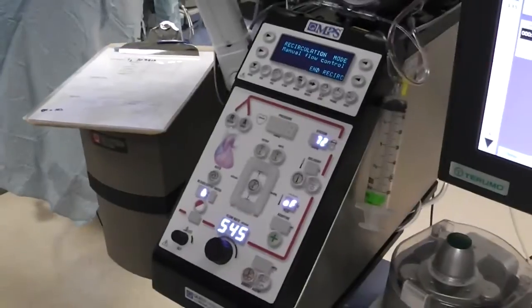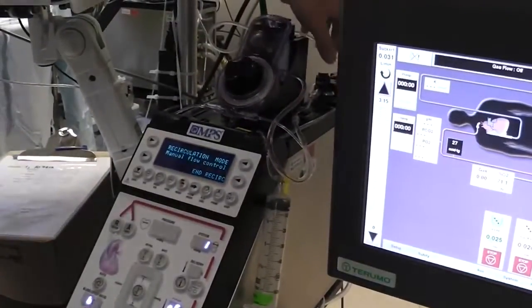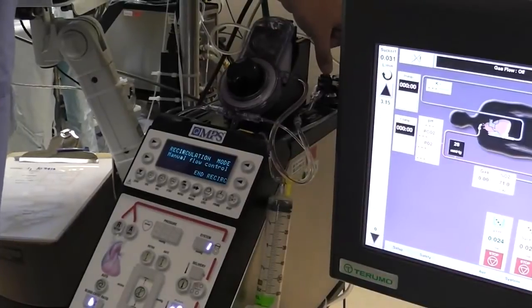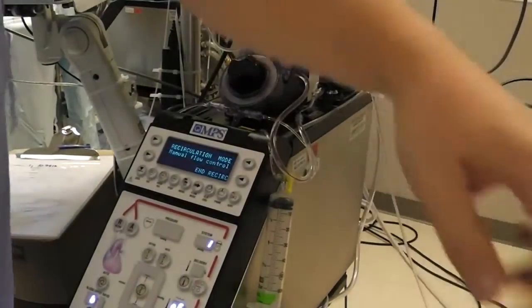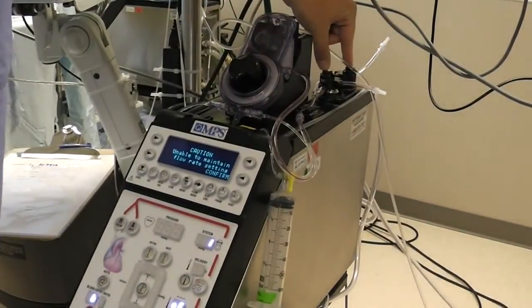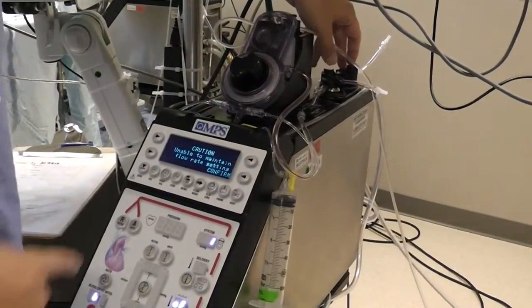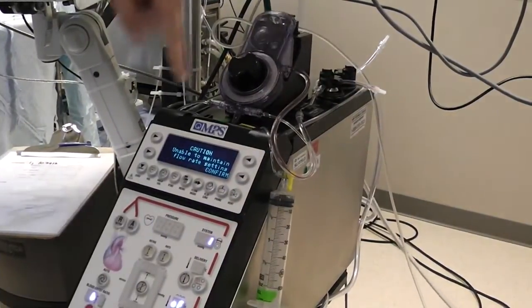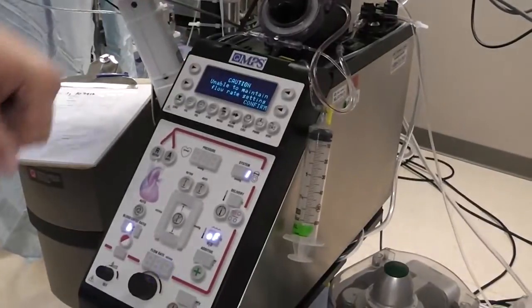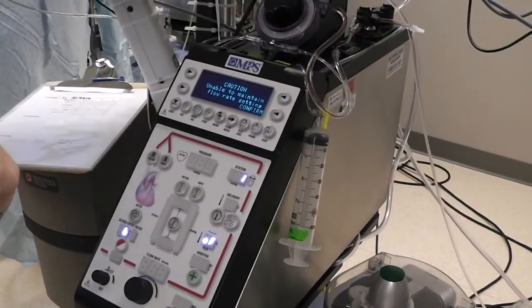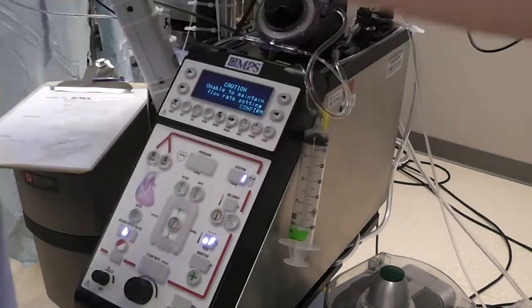You may get some air in the system. If you do that, reach back here and push down on the antegrade and retrograde plungers for these clamps. If you're unable to maintain the flow rate, such as I'm getting here, you need to increase the pressure in the system, either by increasing your pump flow or occluding that venous return line more.